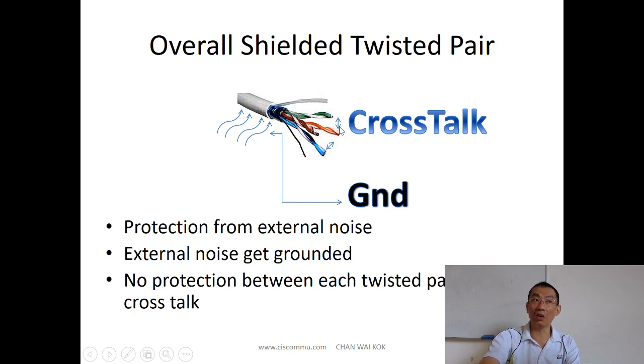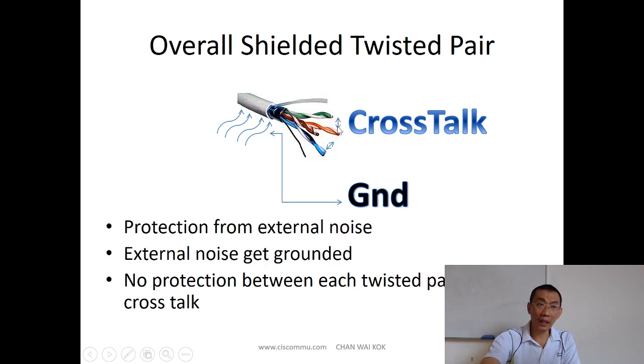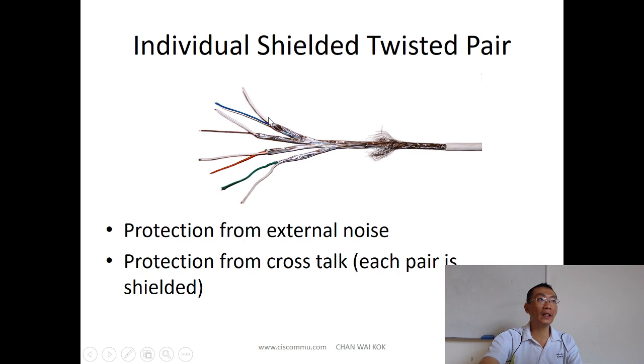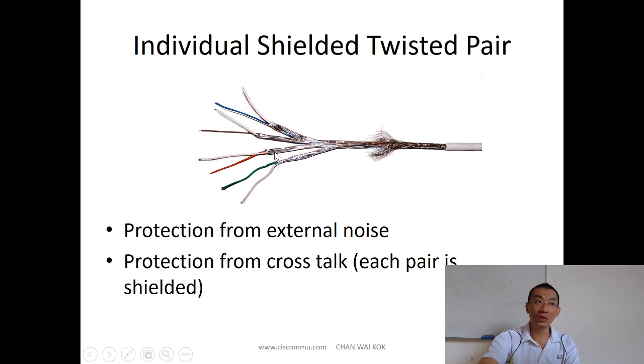However, there can be crosstalk between cables — if the voltage is high enough or there's a cable cut inside. With an overall shielded cable, there's no protection between pairs for crosstalk. But with individually shielded twisted pairs, not only is the overall cable shielded, each pair inside is also shielded, providing protection from both external noise and crosstalk.